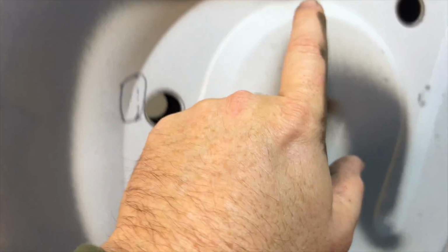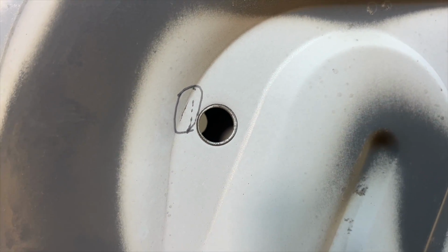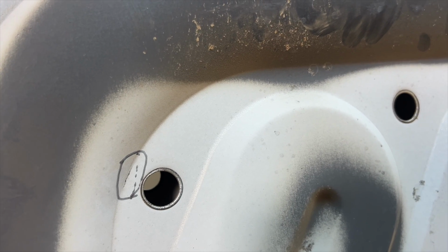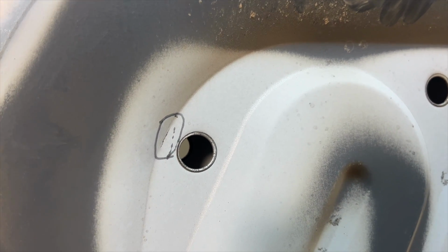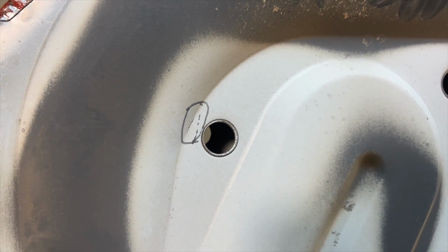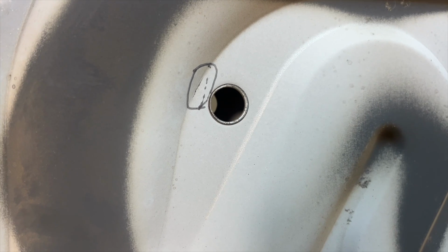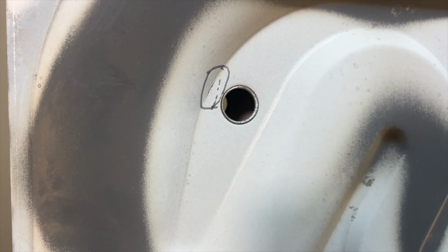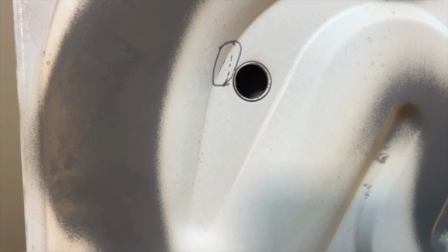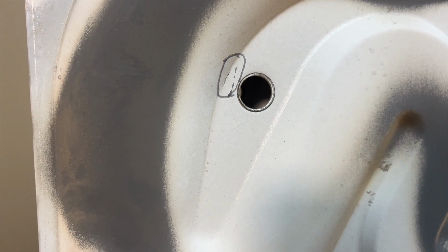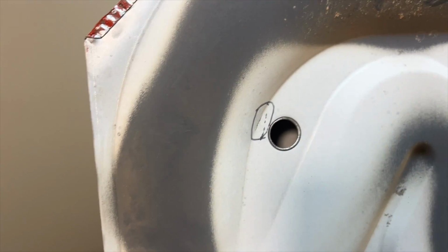Now, if you see a heat exchanger with temperature stress that's super dark, that's usually an indicator that it's overfiring. So you want to check your gas pressure, but at that point, the metal's already been kind of compromised, so usually that means that there's gonna be a crack. So in some cases, you might want to tell your customer, hey, this thing's been overfiring. It's starting to show signs of wear. There is a potential that you could cause a crack. We're going to want to monitor this thing pretty regularly. Every time we do a service, we probably want to pull the heat exchanger and look for it.